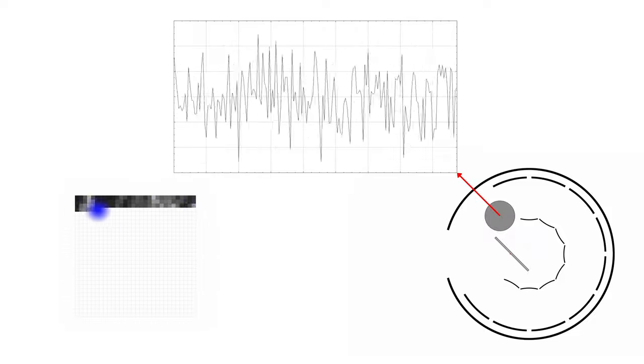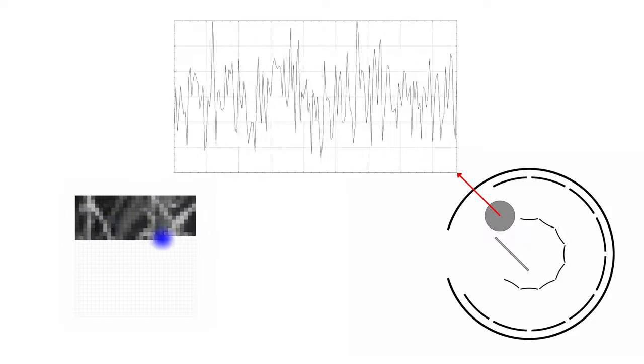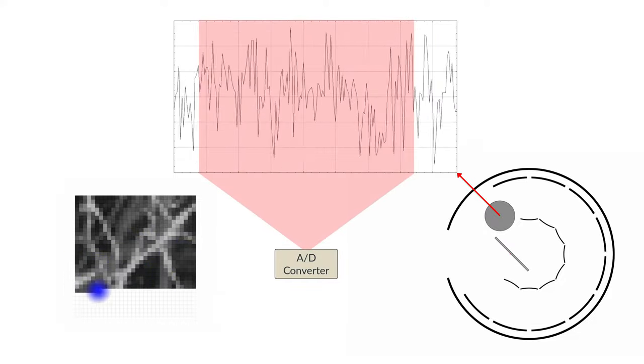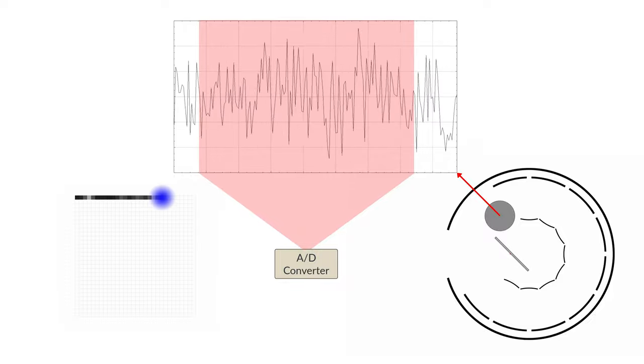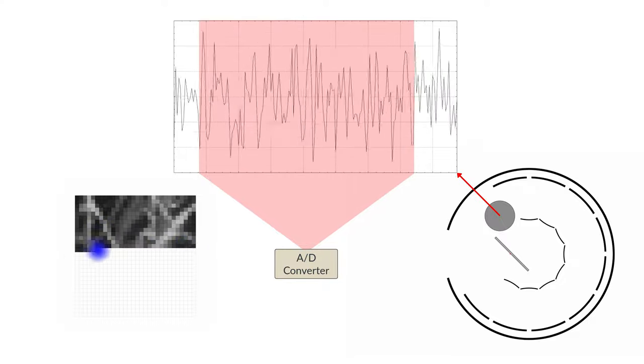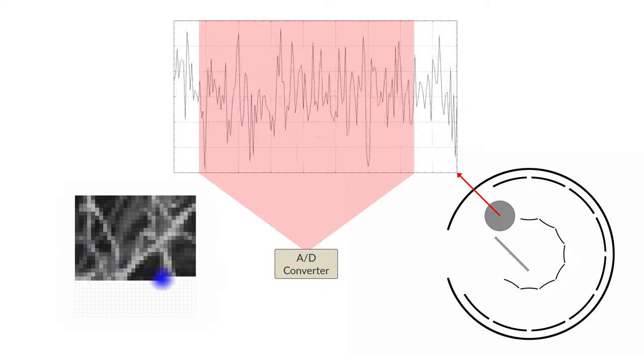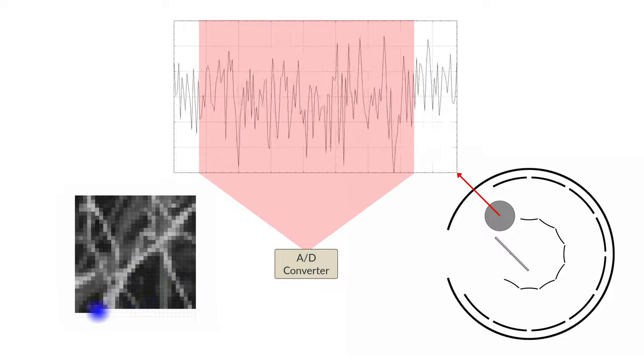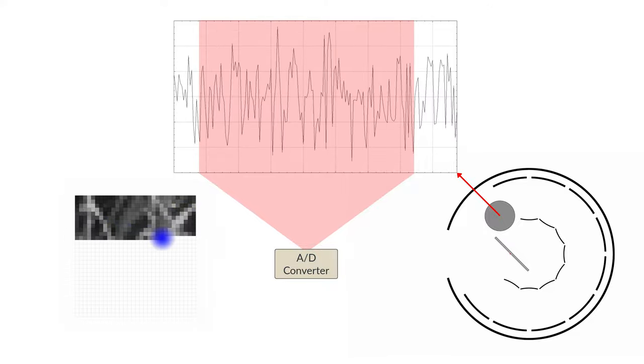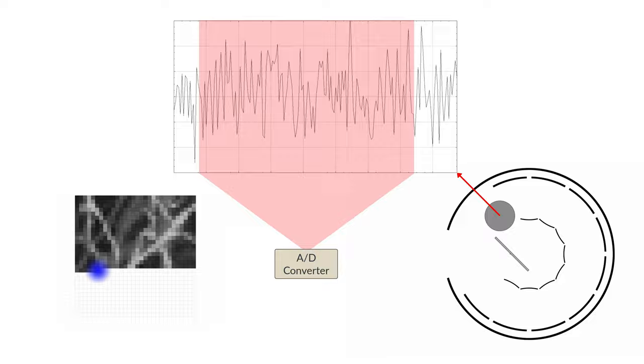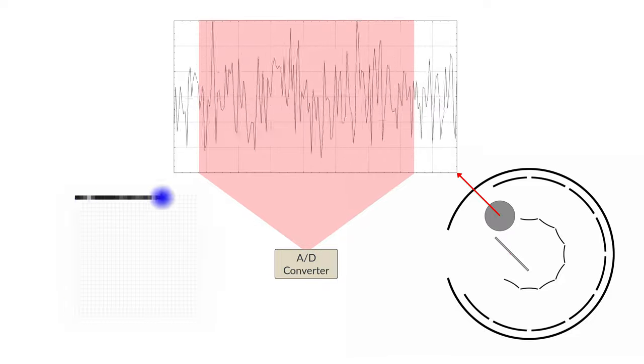PMTs are collecting and outputting this analog current at a much faster rate than we typically scan, so the electronics of the system will periodically sample this current for the amount of time that the laser spends at each pixel in the scan. This is known as the pixel dwell time. The analog to digital converter electronics perform this sampling function, and transform the signal into a discrete, equidistant succession of gray values in the range of the bit depth of the electronics. Each pixel is assigned a gray value in the range of the program depth. That is the intensity of your fluorescence equivalent to the number of photons recorded by the PMT. This data is then output to its corresponding pixel in the image array.